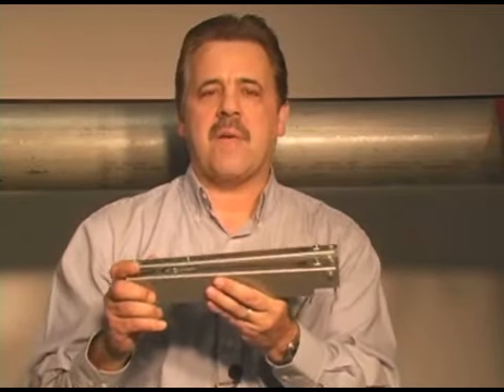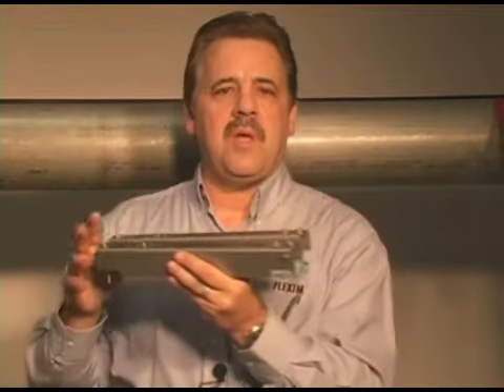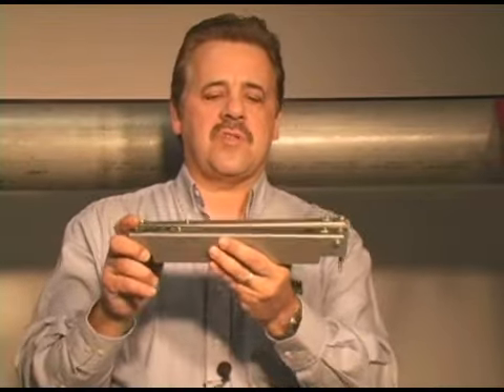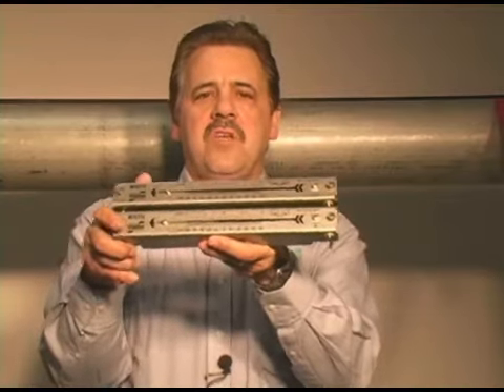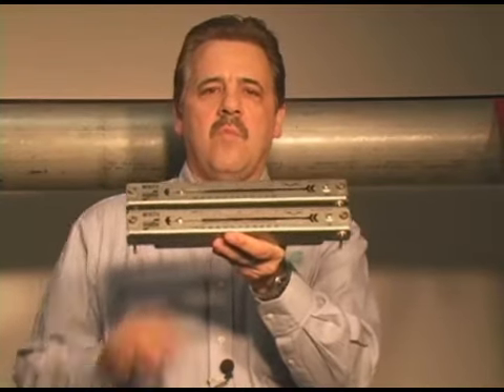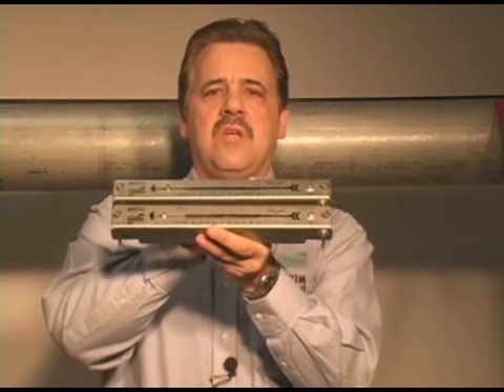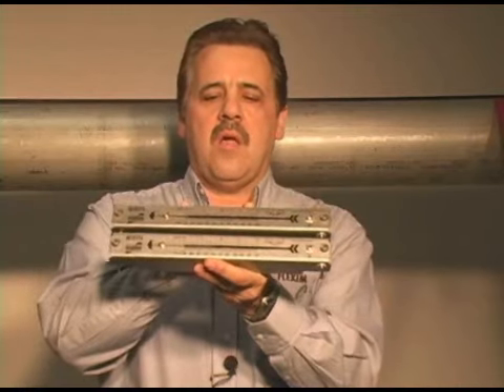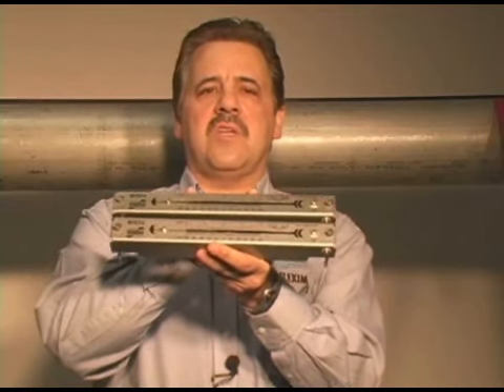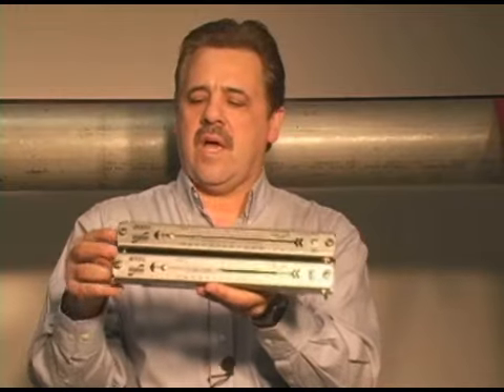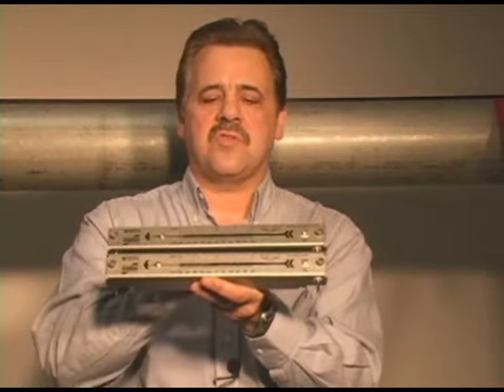When you program up your meter, you're going to get to a point where the meter is going to tell you what the spacing distance of the transducers has to be set at. At that point, you'll stop with the programming on the meter, go to the pipe, and begin the installation of your transducer mount. So now the first thing you have to do is determine what type of mounting configuration you're going to be using, based on what spacing distance the meter has prompted you to set your transducers at.